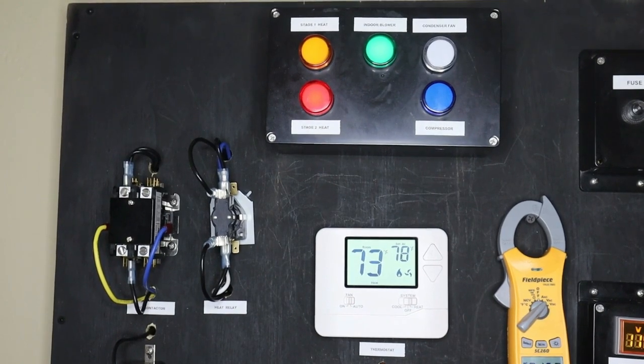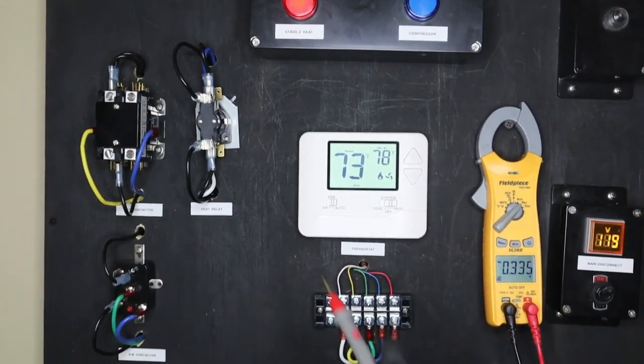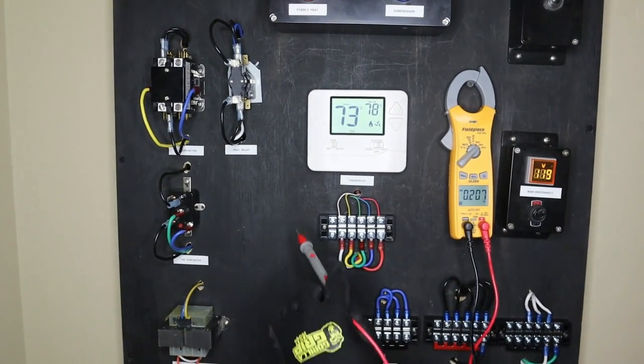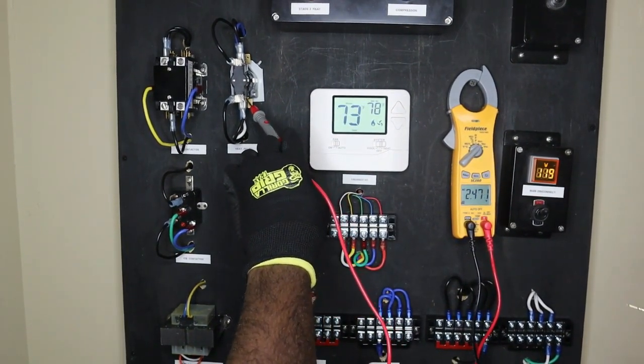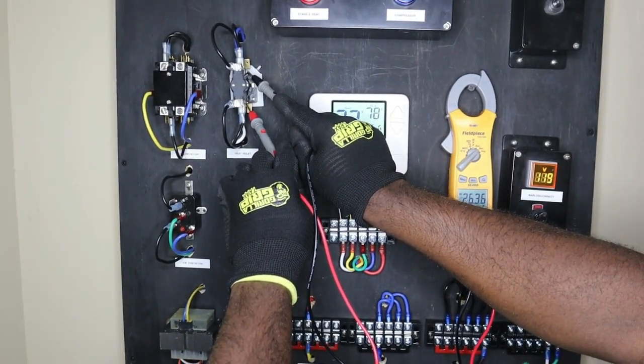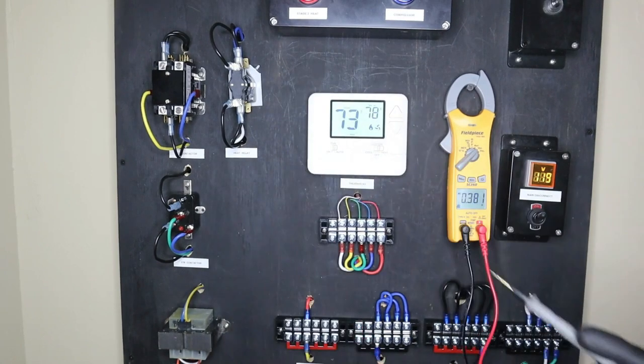Now let's check the control or the coil side of our heat relay. So the white wire from our thermostat sends 24 volts AC to one side of the coil and our blue which is our low voltage common. So as you can see we're measuring 26.3 volts to our coil.